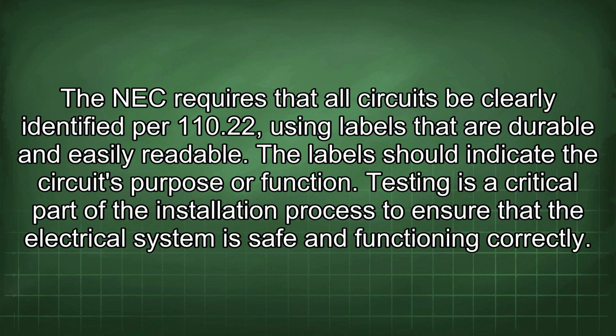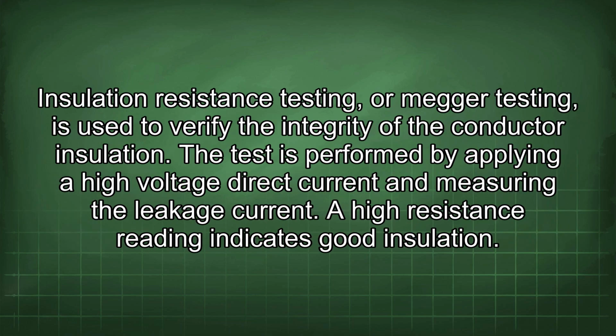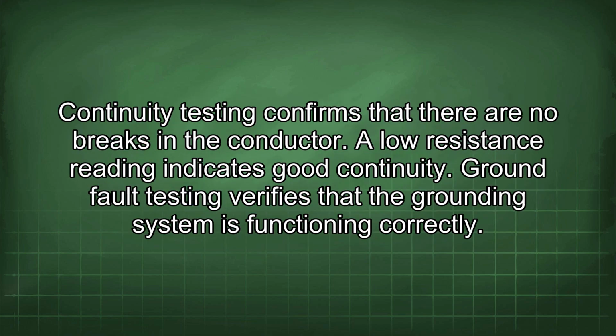Testing is a critical part of the installation process to ensure that the electrical system is safe and functioning correctly. Insulation resistance testing, or Megger testing, is used to verify the integrity of the conductor insulation. The test is performed by applying a high voltage direct current and measuring the leakage current. A high resistance reading indicates good insulation. Continuity testing confirms that there are no breaks in the conductor. A low resistance reading indicates good continuity.